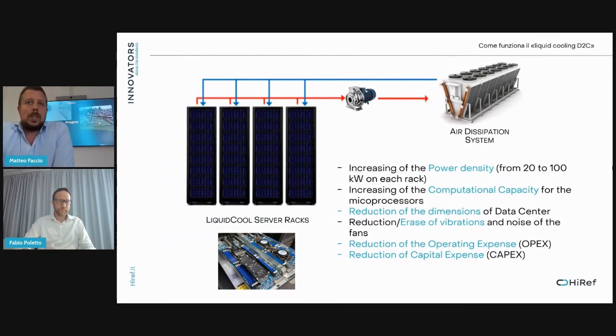On the other side, in terms of retrofit and refurbishment, it's also possible to work on the server racks. We have seen the advent of liquid-cooled servers, and this will become more and more popular in the next years. With this type of new technology, we can increase the power density, driving also an increase of the computational capacity and reducing the cost of the system. Our role in this new scenario will be to manage the cooling water production, the cooling water distribution, and also to give the customer the possibility to manage the heat dissipation from the data center.